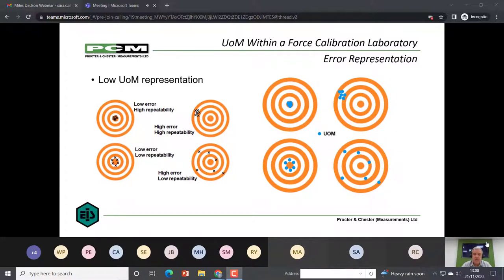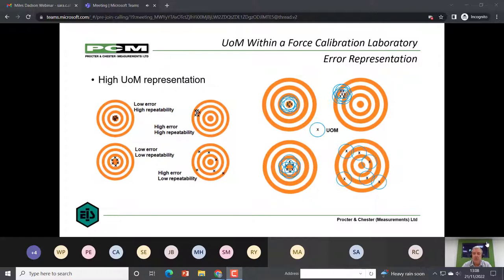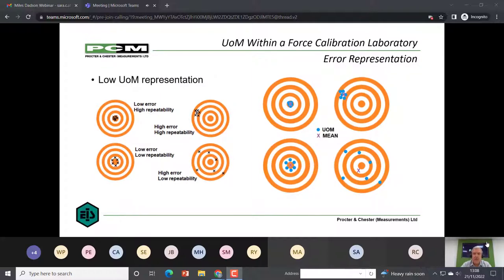With most calibrations, you'll carry out more than one measurement. Here we have five, quite common to have three. And so if you put the mean, so you take the mean of all the different values, here we have top left will have a mean right in the middle of the target, but so will bottom left have a mean right in the middle. On the bottom right, you have a very large scatter of results, very poor repeatability, but you still have a mean that is very close to whatever the true value is.